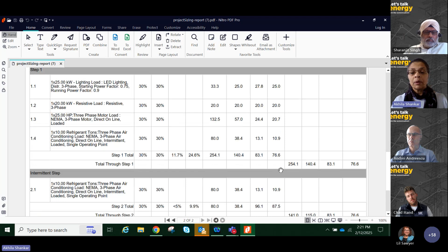On the second page, you will see the list of loads that has been entered, the permitted voltage and frequency dips, and what the actual voltage and frequency dip is. Since I put all of the loads in one step, that's what you're seeing, the total load for step 1.